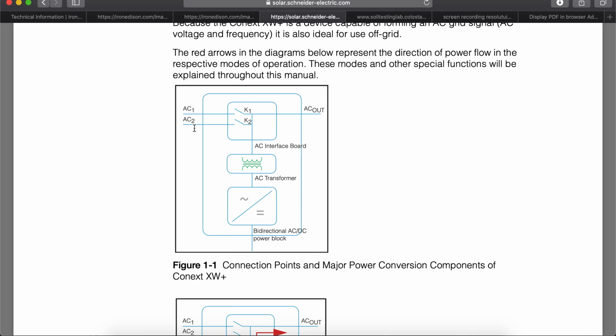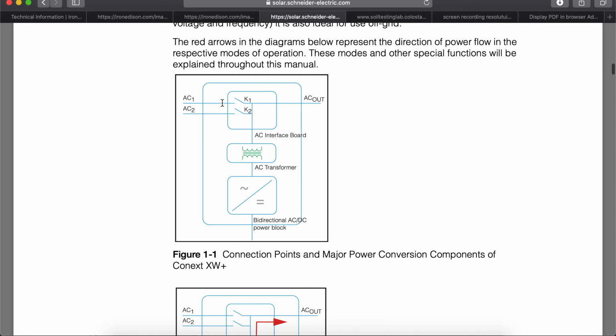AC1, AC2 inputs are controlled by the relays K1 and K2 that would either allow the inverter to pass energy through by inverting, or to simply pass through from AC input to AC output. This is AC coming in. Here's the AC interface board, AC transformer, and then the bidirectional AC-DC power block, so the battery would be connected down here. The loads would be connected over here. The grid or gen would be connected over here.